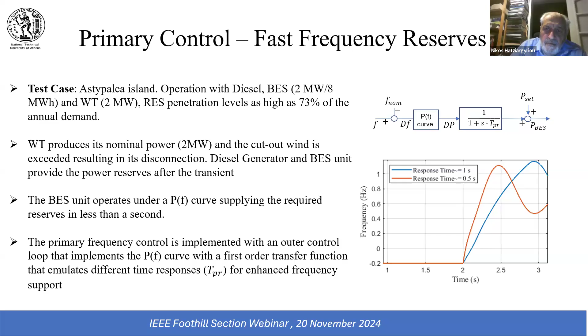So the studies have modeled this primary frequency control with a control loop that implements the droop curve and the first order transfer function to emulate the different time responses. And you see how the frequency changes depending on the response time of 1 or 0.5 seconds. In fact, this is opposite, okay, because you have a drop of frequency since you lose the largest wind turbine.